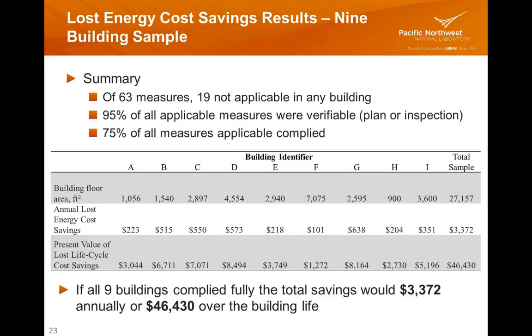Of those that were applicable, 95% were verifiable, either through plan review or inspection they were able to tell the condition of the measure. 5% they could not tell at all. And of those that were verifiable, 75% complied. So thinking in terms of the old DOE methodology, pass-fail, this sample of 9 buildings would have scored a 75% compliance rate. But as we discussed, we're interested in some different results here, and that's what's shown below.